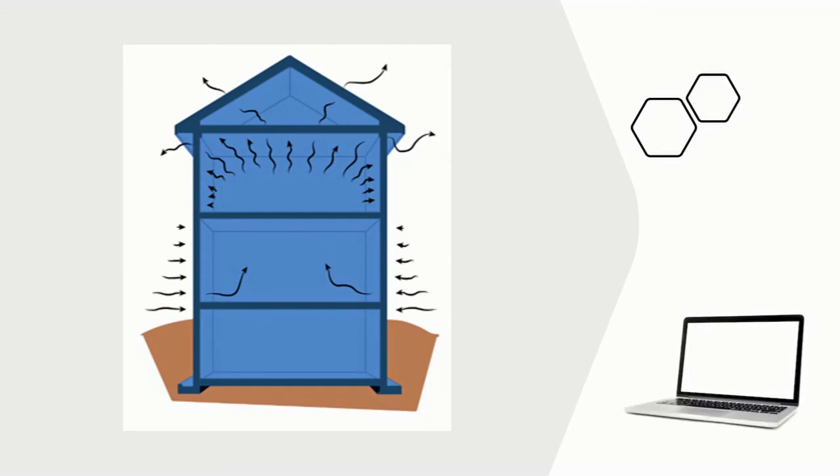It's been a code requirement to do an F280 load calculation to size heating and cooling equipment since 2015 for new construction and retrofits. If your contractor says they have enough experience without calculations or uses a square foot method, be careful. Demand code compliant calculations.